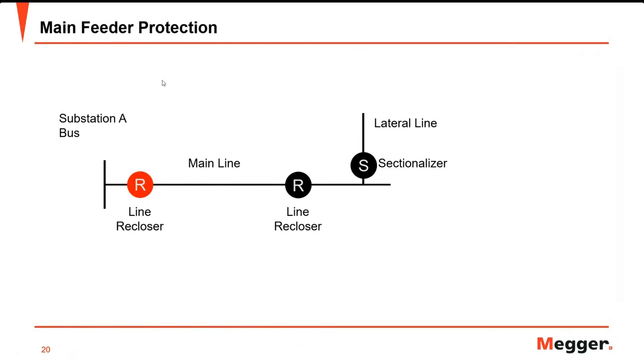Main feeder protection: since the combination of a line recloser and its control is cheaper than a circuit breaker with a separate relay, reclosers are sometimes used where the required continuous current or available fault current is not very high, because most reclosers have smaller ratings than circuit breakers.